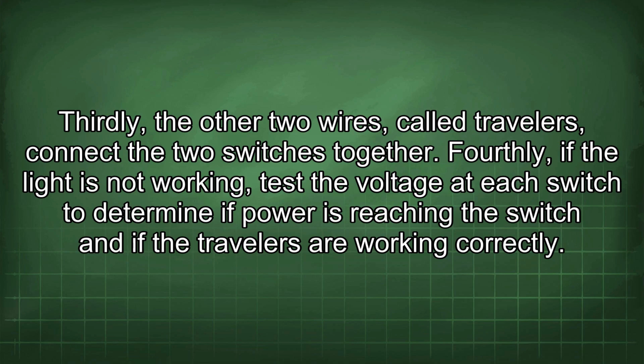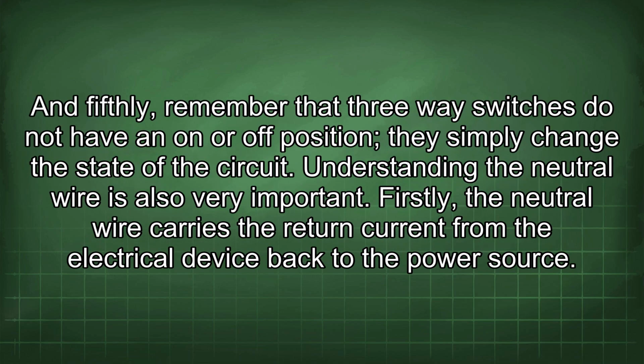Fourthly, if the light is not working, test the voltage at each switch to determine if power is reaching the switch and if the travelers are working correctly. And fifthly, remember that three-way switches do not have an on or off position. They simply change the state of the circuit.